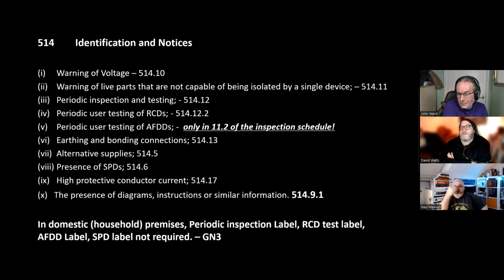I think this is an error. So for those who are looking for mistakes, the requirement for the AFDD label only appears in the inspection schedule. It appears nowhere else, but it's stated as a requirement in Guidance Note 3. So it's an error in Guidance Note 3, and it's technically not a requirement unless you take an informative inspection schedule, which isn't a normative requirement. So it's wrong. Anyway, carry on. So earthing and bonding, alternative supplies, surge protection devices, high protective conductor currents, and the presence of diagrams, instructions, similar information. So all of those things which you're fairly familiar with.